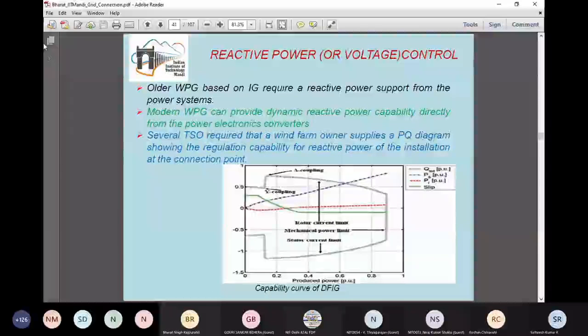Next slide, please. Yes. So this slide gives us the capability curve of a doubly-fed induction generator. We will discuss this capability curve. We are aware that we have studied the capability curve of a synchronous machine, the synchronous generator, but such a curve was not earlier available for induction generators or induction machines. But with a power electronic converter, it is very much possible that an induction machine is able to absorb as well as give reactive power.